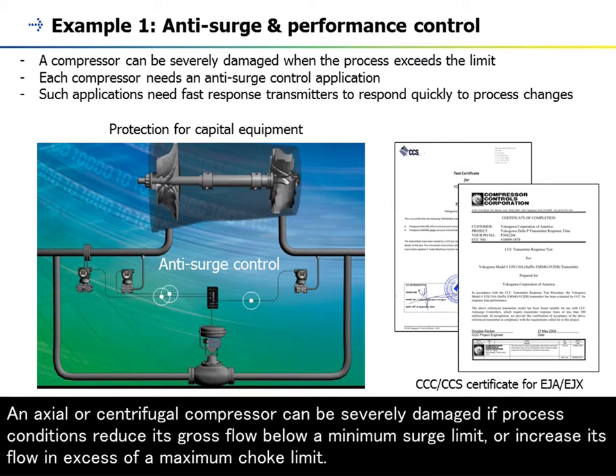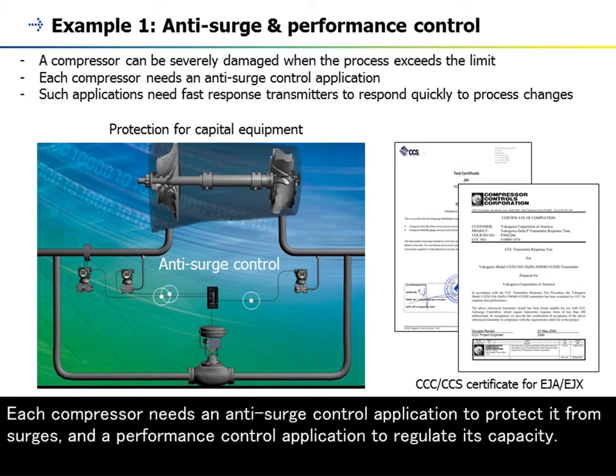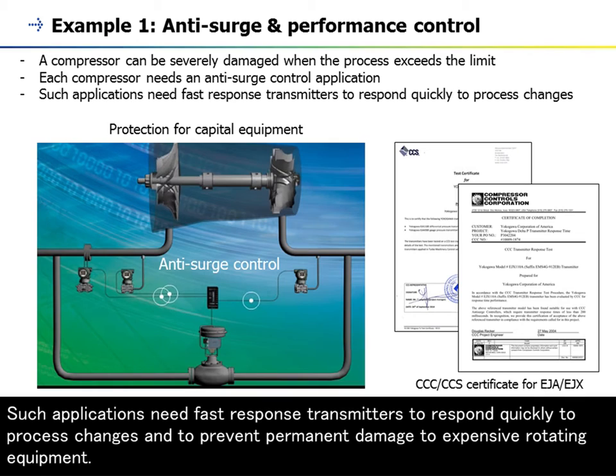An axial or centrifugal compressor can be severely damaged if process conditions reduce its gross flow below a minimum surge limit, or increase its flow in excess of a maximum choke limit. Each compressor needs an anti-surge control application to protect it from surges, and a performance control application to regulate its capacity. Such applications need fast response transmitters to respond quickly to process changes and to prevent permanent damage to expensive rotating equipment.